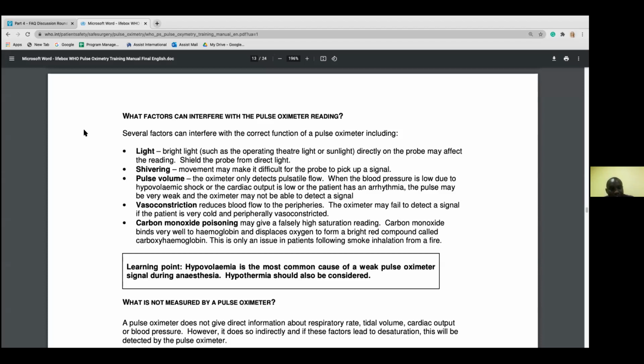And then in other conditions such as carbon monoxide poisoning, this may give a falsely high reading of the oxygen saturation. And so you need to be very, very careful as you are interpreting the SpO2 in a patient with suspected carbon monoxide poisoning. So these are some of the things that may interfere with the accuracy of the reading. So it's very, very important for us to get an accurate reading and interpret it correctly, because it makes a difference in the management of the patient.